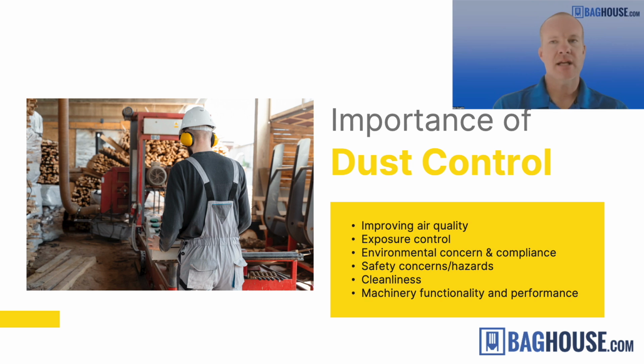Depending on the size of the shop, if it's anything bigger than a garage hobby shop, you also have some regulatory requirements - OSHA requirements, and NFPA, which defines all the requirements for combustible dust. If you have a wood shop, it's pretty well guaranteed that you fall under the NFPA 660 and 664 requirements for combustible dusts, because wood is combustible dust. So you have to comply not only with OSHA's general duty clause and all the OSHA requirements for dust collection and combustible dust, but you also need to be aware of NFPA and make sure you have the right safety devices and controls in place for your wood shop. So that's regarding combustible dust.